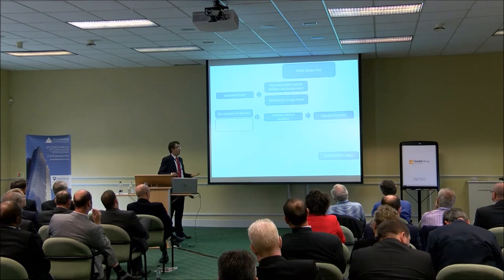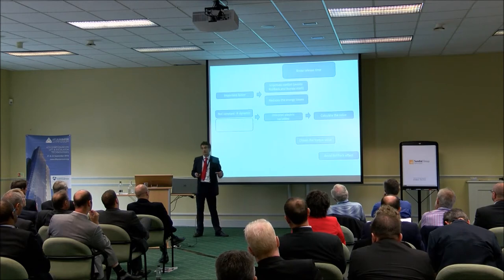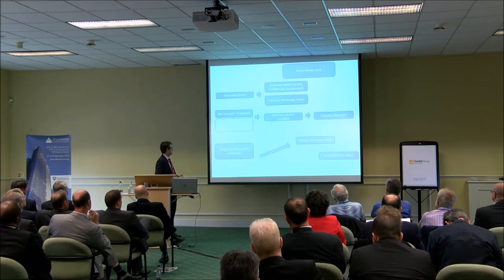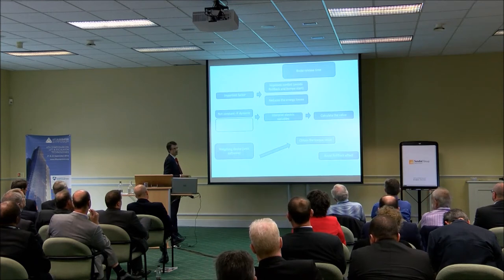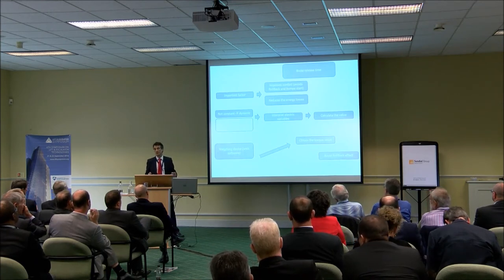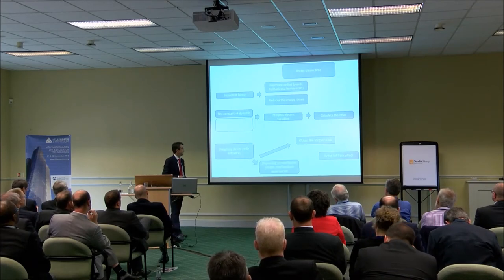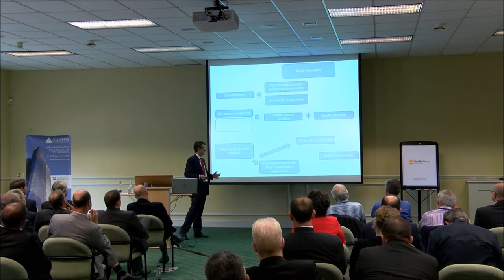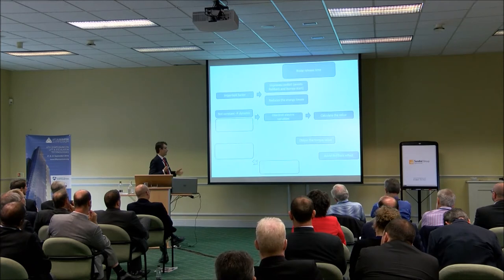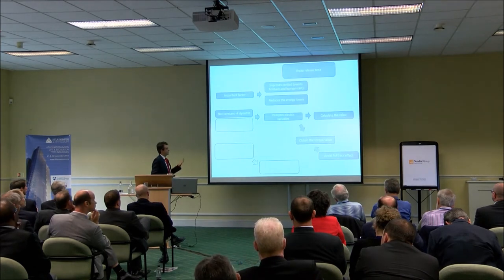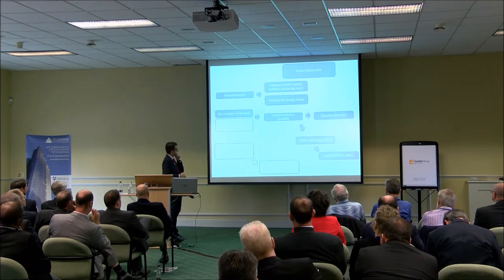If we talk about the rollback effect, we know we need to obtain the torque value in order to avoid it. Traditionally we can use weighing devices and with some software know the torque demand before releasing the brakes. But depending on mechanical designs, sometimes we find malfunctions. So we suggest using electric variables instead of the weighing device to calculate this value.